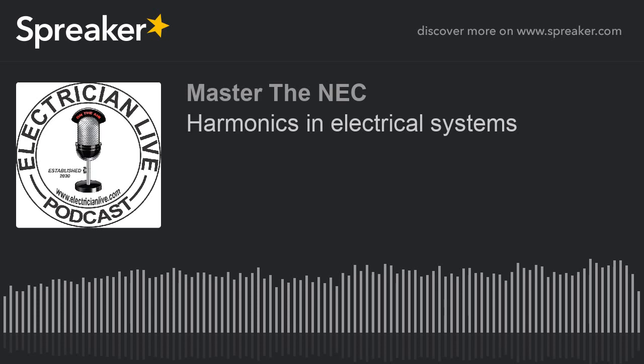So that's what we're going to talk about today, harmonics and the problems that can be caused in many industries by harmonics. Now, what are some of the problems that can happen with harmonics? They can range anywhere from overheating conductors, and we'll talk about that in a minute when we talk about 4-wire, 3-phase, Y type of transformer setups and the conductors that come from the secondary. But yes, transformers in itself, sometimes harmonics, which is an elevated frequency, actually it's the multiples of the fundamental power frequency, and we'll talk about that in a second, but it can cause breakers to trip when they're nowhere near the capacity of the breaker.